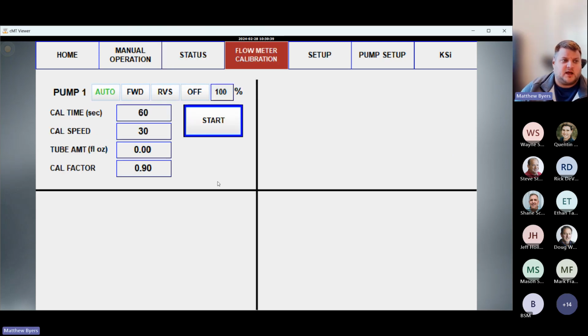Flow meter calibration. If you have more than one pump, and I know some of you do, you'll see pumps 2, 3, and 4 in the grid. But again, to calibrate these pumps, we need to put the pump in forward, get that cal tube up to 0. For our time and speed, we want that cal tube to be as full as possible without overflowing. Typically, 180 seconds at 20% speed should take care of that. Once you've got your speed in there, you can press start.